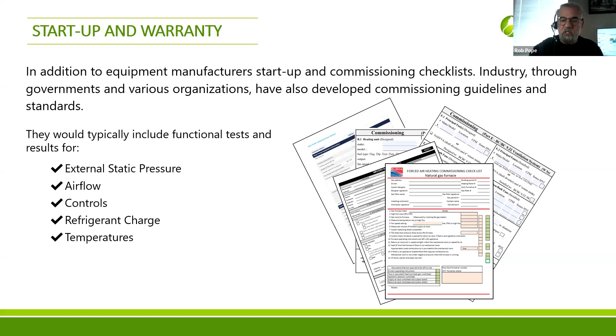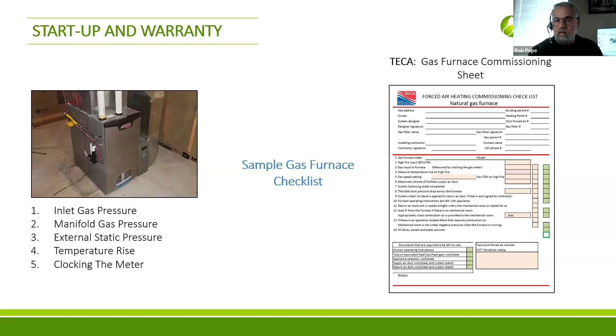Here's an example. If you have a dual fuel system, this is a checklist from TECA, a BC organization. Some of the things you'd be checking for—not all of them—are inlet gas pressure, manifold gas pressure, external static pressure, temperature rise, and clocking the meter. There is a form out there for this; TECA has one, HRAI has one. Or you could get a generic one online, but I wouldn't recommend it.